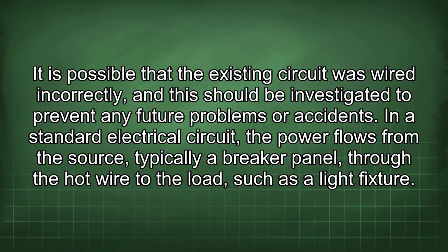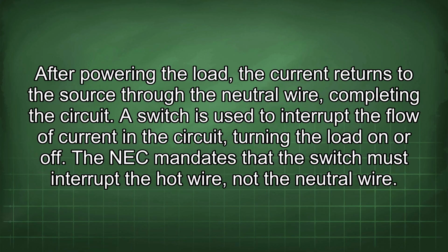In a standard electrical circuit, the power flows from the source, typically a breaker panel, through the hot wire to the load, such as a light fixture. After powering the load, the current returns to the source through the neutral wire, completing the circuit. A switch is used to interrupt the flow of current in the circuit, turning the load on or off. The NEC mandates that the switch must interrupt the hot wire, not the neutral wire.